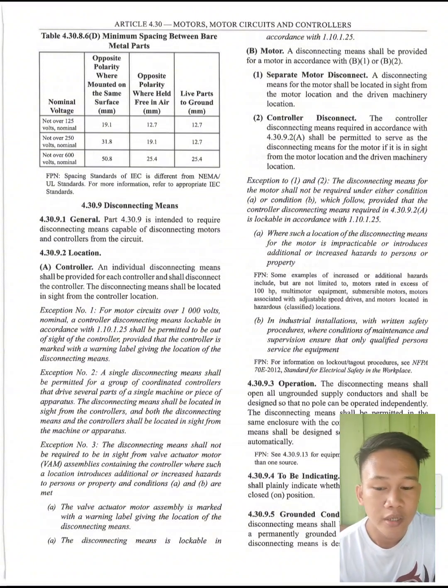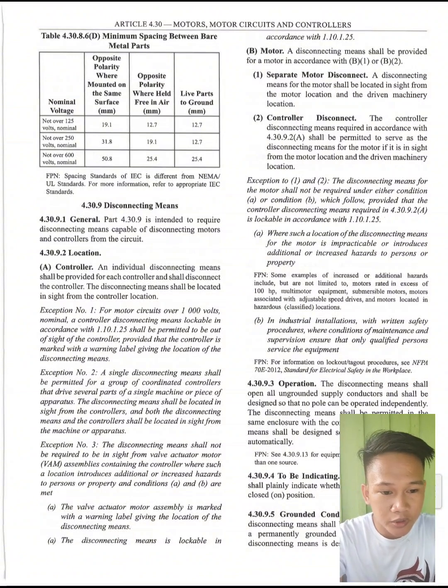So, now another exemption. Exemption to 1 and 2. The disconnecting means for the motor shall not be required under either condition A or condition B which follow, provided that the controller disconnecting means required in 4.30.9.2a is lockable in accordance with 1.10.1.25. Where such location of the disconnecting means for the motor is impracticable or introduces additional or increased hazards to persons or property. Next is industrial installations with written safety procedures where conditions of maintenance and supervision ensure that only qualified persons service the equipment.